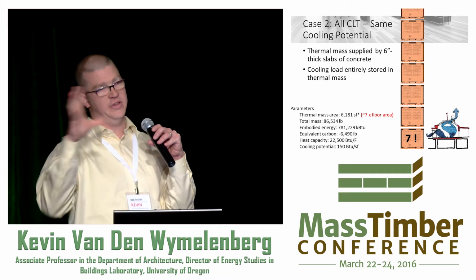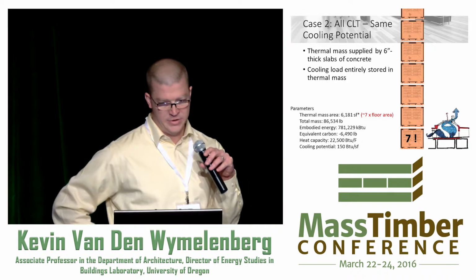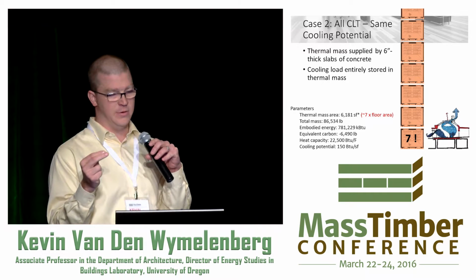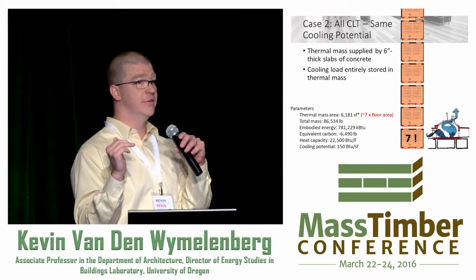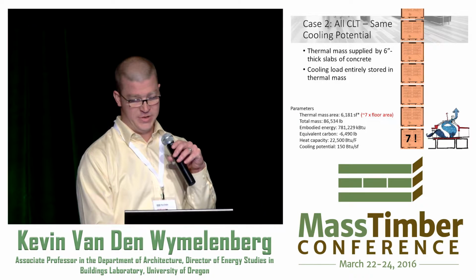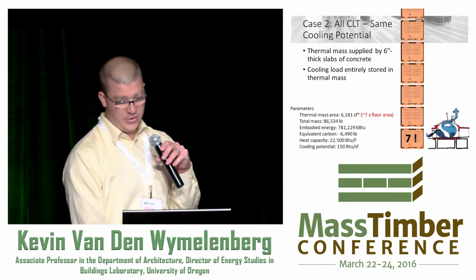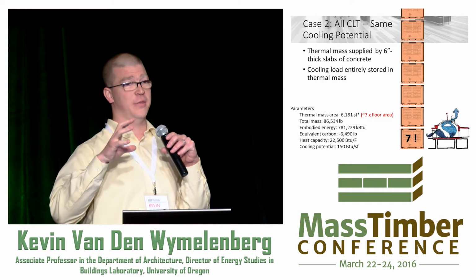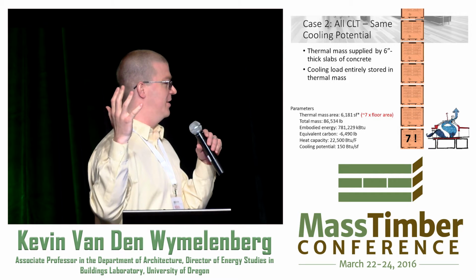What happens if we go all CLT everywhere? I'll talk a little bit about some of my assumptions here underneath the hood if you're interested. But we realize that if we want to have just all CLT everywhere, we need to design a building that's 1/3 of that already very low internal heat gain. So your target is 50 BTU per square foot if you want to achieve it all with the thermal mass from the CLT alone. If we want to look at the 150 BTU load, the more realistic load, we're talking about a theoretically impossible answer: 7 times the floor area as available exposed CLT. We can't do it.